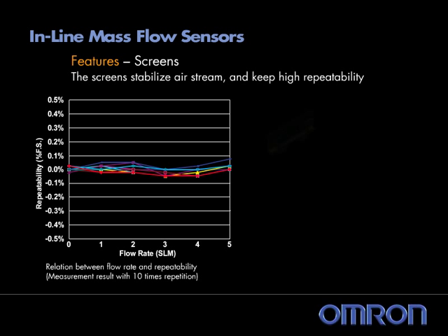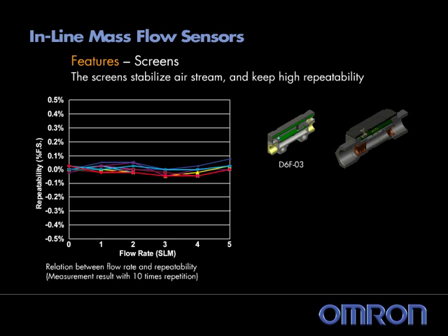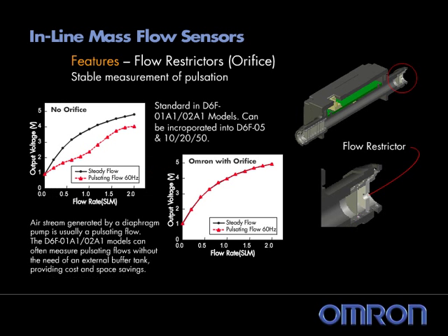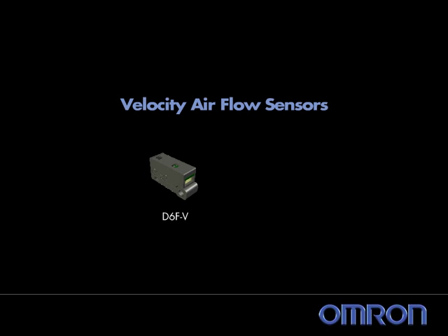The inlet screens are used to ensure a uniform flow over the sensing element by smoothing out turbulent flow, resulting in very high repeatability in the field. All OMRON flow sensors are individually factory calibrated prior to shipping. The D6F-01A1/02A1 series flow sensor incorporates an orifice that helps smooth pulsating flow patterns, often eliminating the need for a buffer tank.